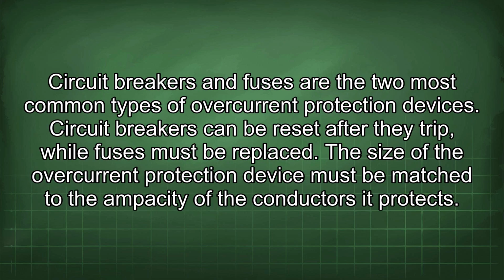Circuit breakers and fuses are the two most common types of overcurrent protection devices. Circuit breakers can be reset after they trip, while fuses must be replaced. The size of the overcurrent protection device must be matched to the ampacity of the conductors it protects.